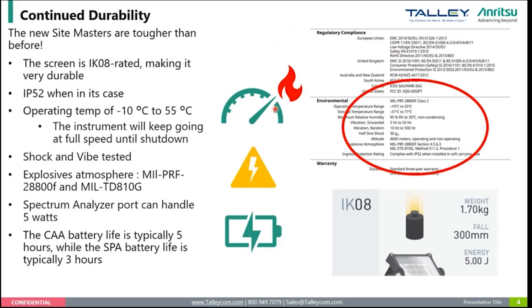It's shock and vibe tested, just like I see here in our data sheet, so it will be able to survive all the shock and vibe. And for those in explosive environments, just like our other instruments, it is tested to withstand those environments, to not have any accidental discharge and ignite anything. On the spectrum analyzer side, one of the most common things we hear is that they are too close to the base station and someone fires up a radio and they burn out the port. We've made sure the spectrum analyzer here has 5 watts protection. Of course, that's for a limited time, so you can't key a radio indefinitely into the instrument, but we maximized the protection as much as we could without compromising the accuracy and battery life of the instrument.